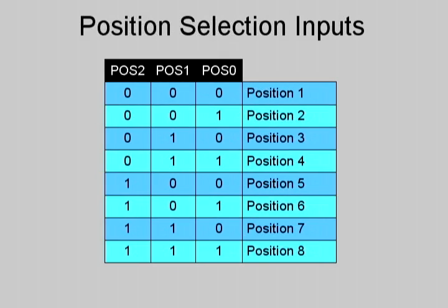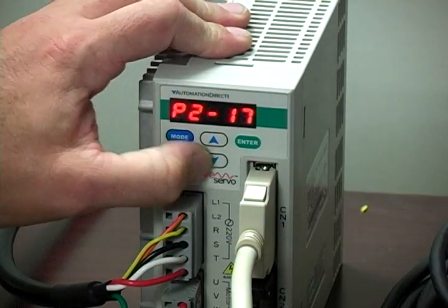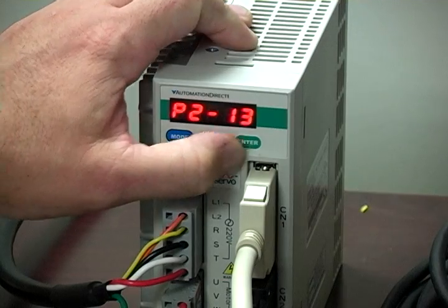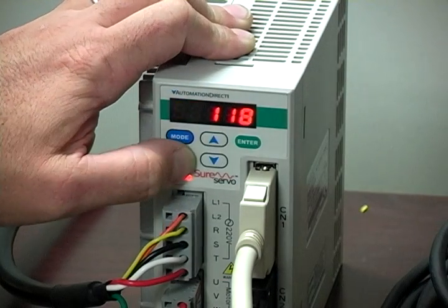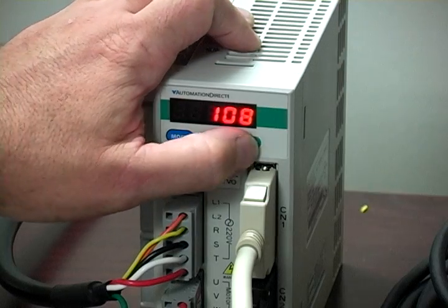To save digital inputs for other uses, not all of the position selection inputs have to be configured. If only two set points are needed, for example if the motor needs to move and then return, only one position selection set point needs to be configured. Configuring only one input, 2 for example, with POS0 and POS1 not assigned, would allow the selection of POS1 and POS5. We also need to set digital input 4 to be the command trigger by setting P213 to 108. This trigger will actuate the movements.